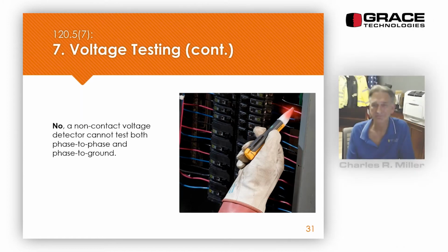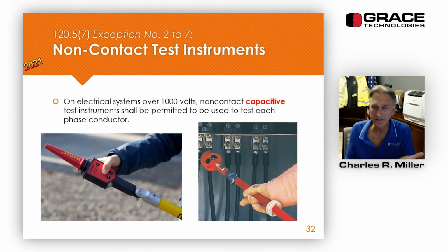Thanks, Charlie. All right, so several editions back, this type of tick tracer, a medium and high voltage tester, was not even in 70E. Finally, it was added in. It says on electrical systems over 1,000 volts, non-contact capacitive test instruments are permitted to be used to test each phase conductor. Now, the change in the 2021 edition, well, I'm on the 70E committee, so I guess I can say we added capacitive to this section.